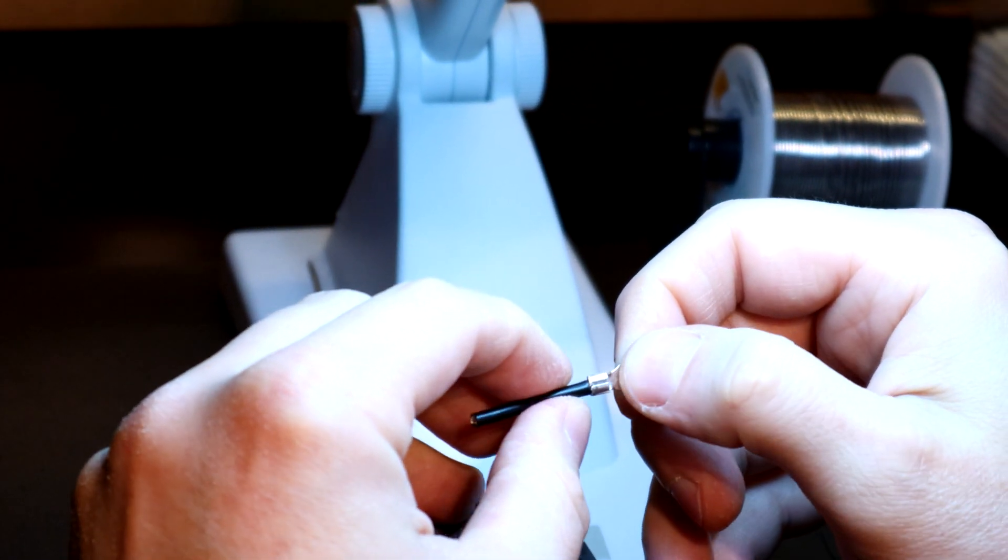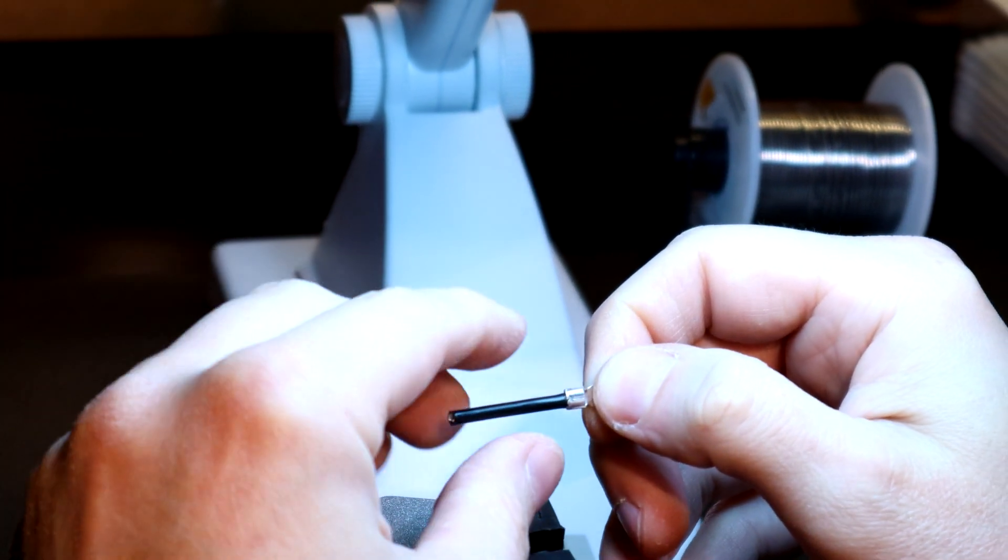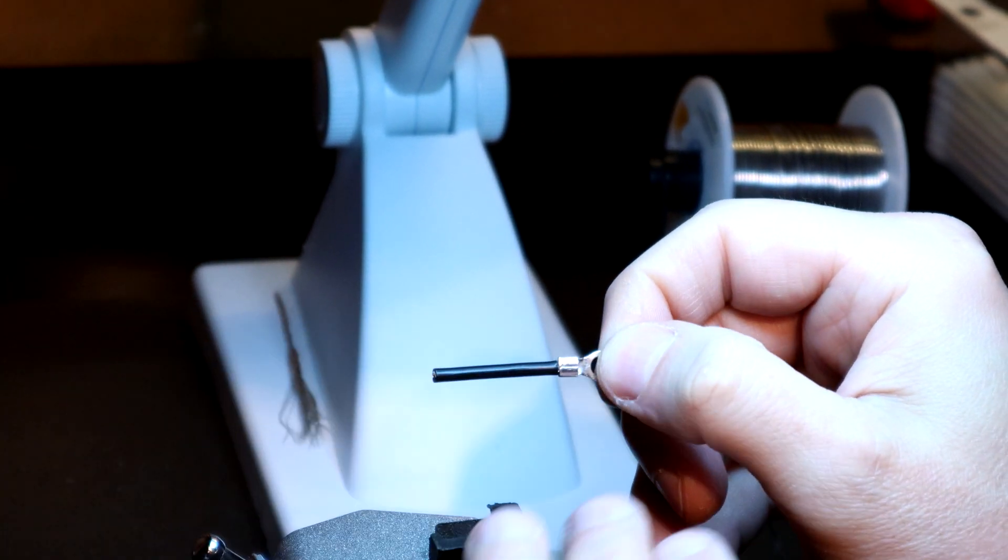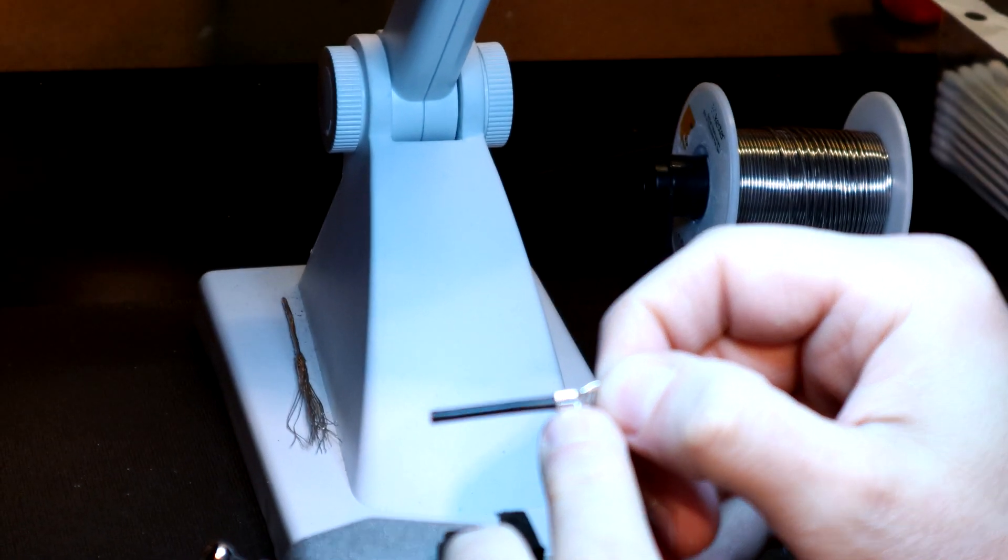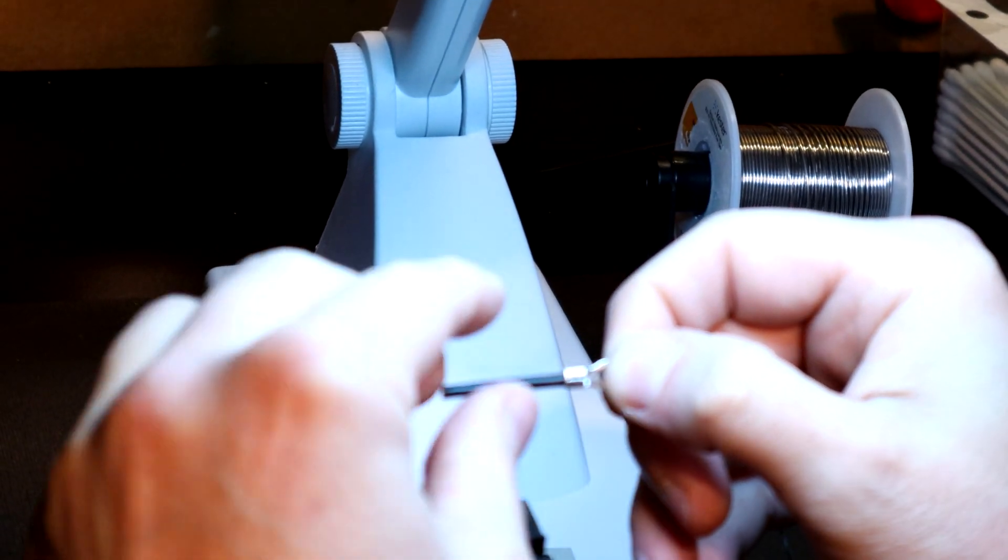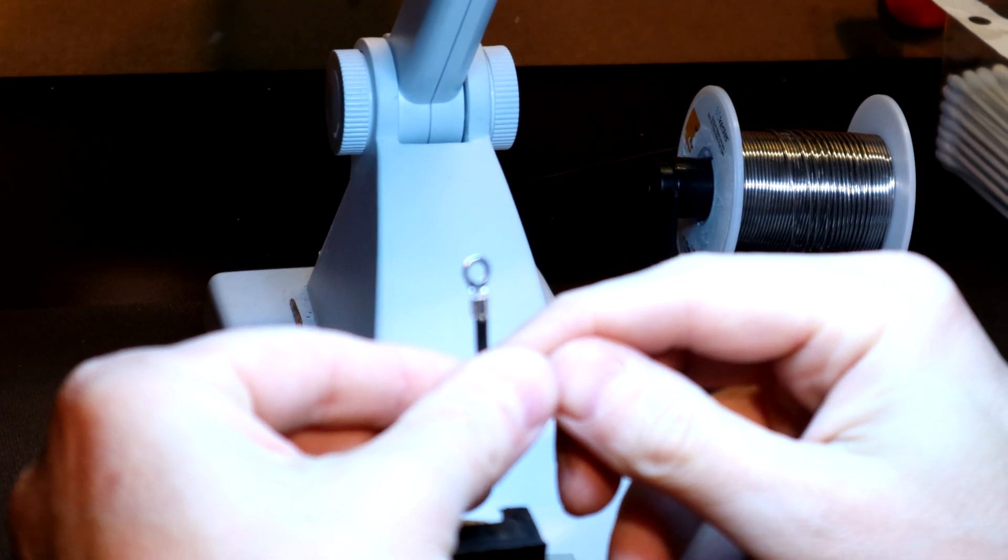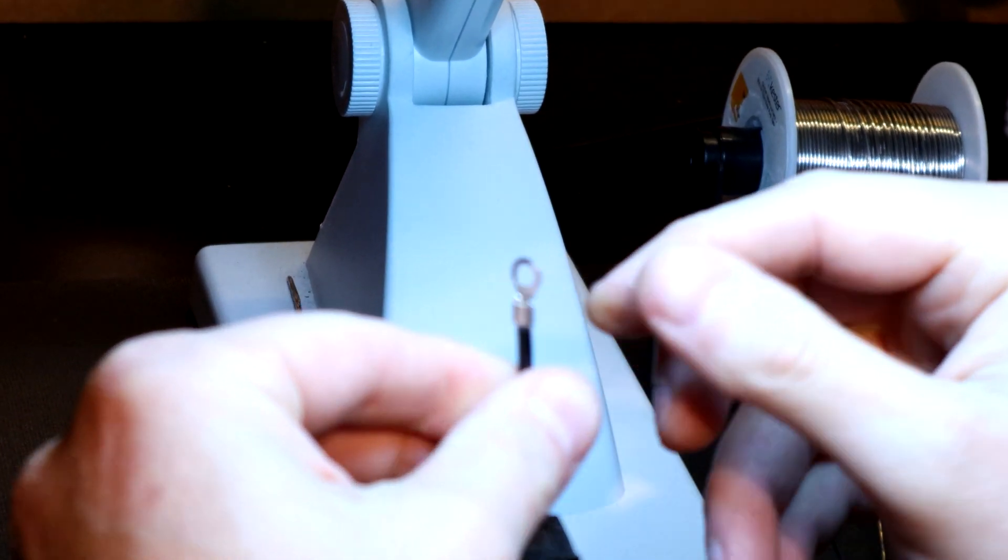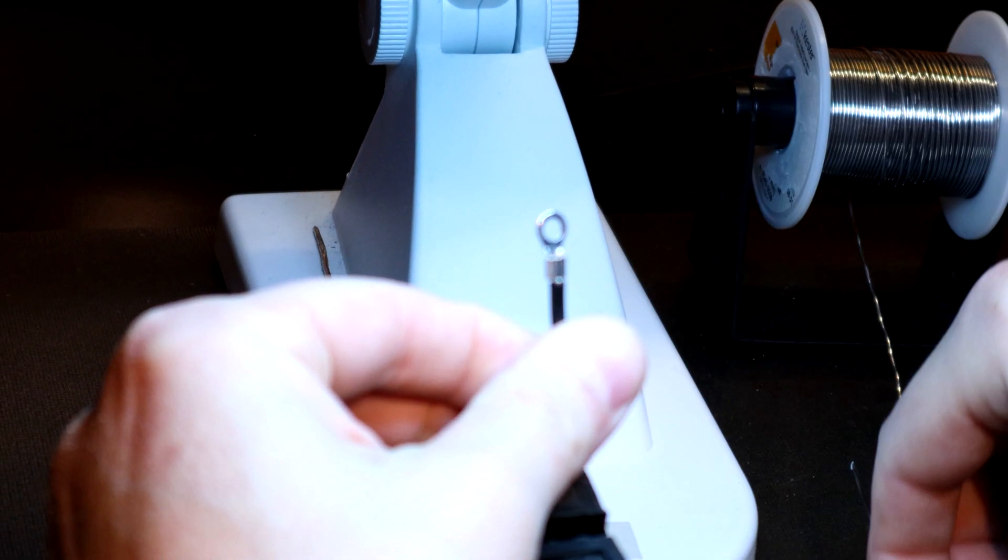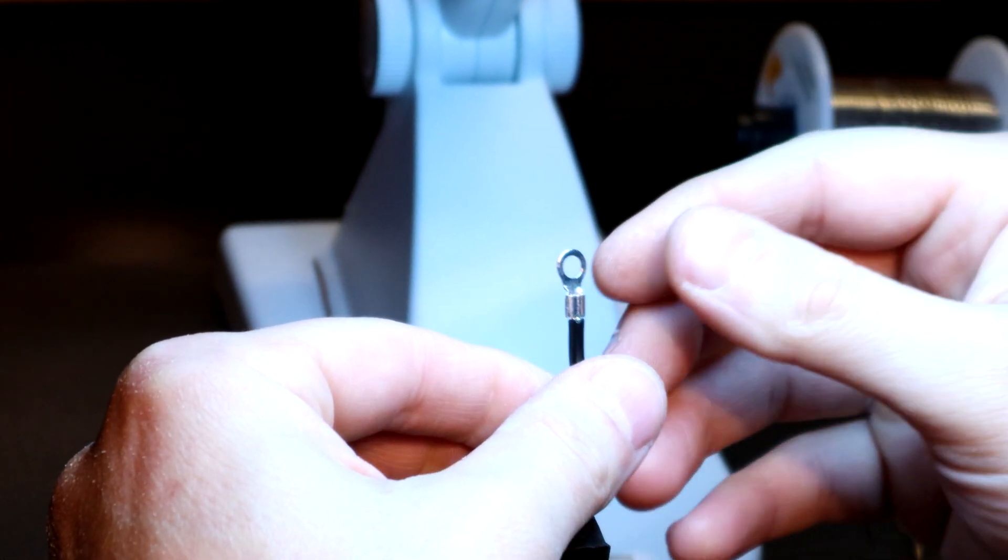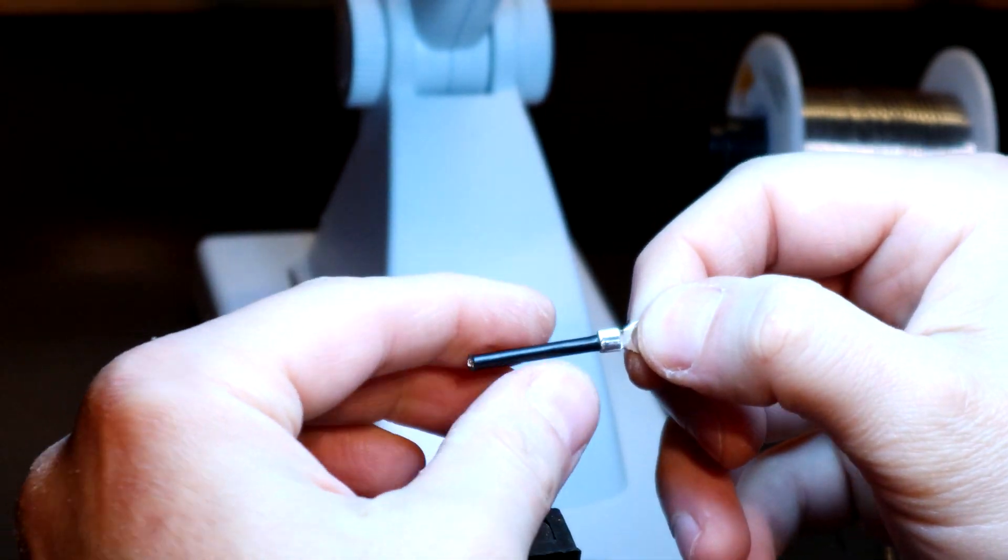So, if you can see that, what we're going to do now is this is number one reason why I'm not a fan of crimp connectors. Now, I know some guys will say, well, that's not every crimp connector. That's not this and that. It scares me to think that this was done with a crimp tool properly. It's totally symmetrical in form. The connector looks perfect. Everything there is correctly done. And I've had end users tell me that. I've done everything correct as to the instructions on the tool itself. And that's what happens.